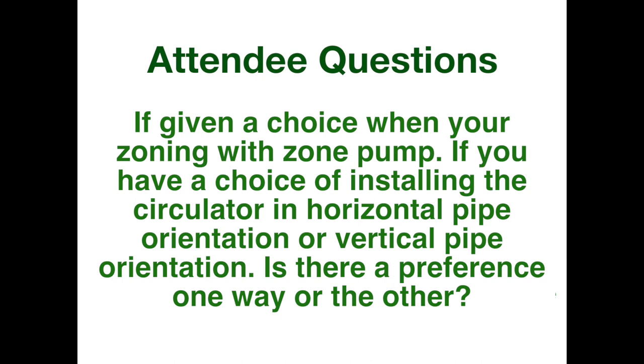All right, Mark. Bob, we have a number of pump manufacturers on the webinar, and several still on. One of them just confirmed what you just said about the orientation of the pump, horizontal versus vertical, and the checks. There's a classic example, one that isn't put vertically, and maybe there's not a check in it, because the checks that come with the pumps now, you can take them out. They used to come in the box separately, and then you could either put it in or leave it out. Most of them I've gotten recently have the checks in there, but you can reach in with needle-nose pliers, pull them out, and if you don't need or want the check, like the guy that put the zone valve after the pump, obviously he didn't need the check valve. So I think that clears that up a little bit. And thanks to the pump people for chiming in.